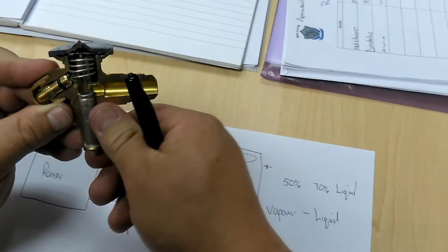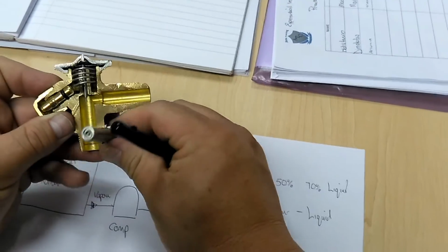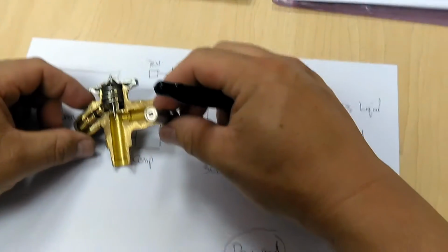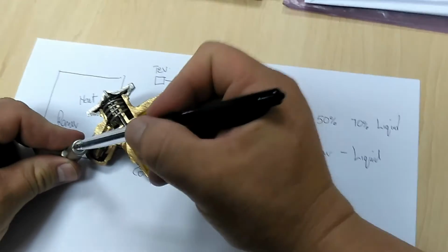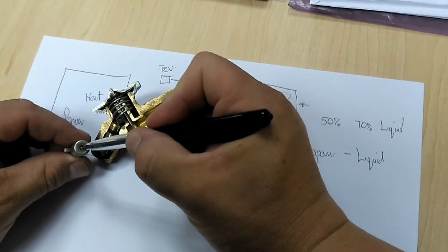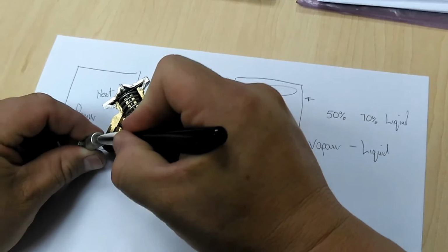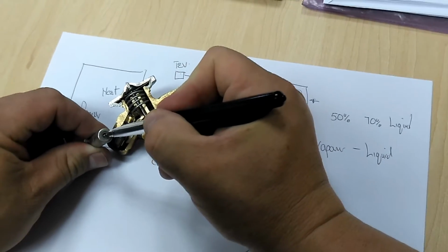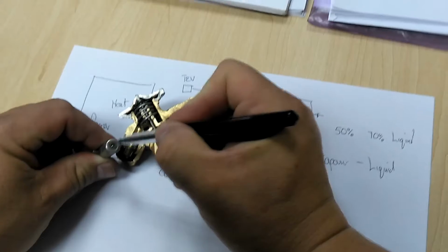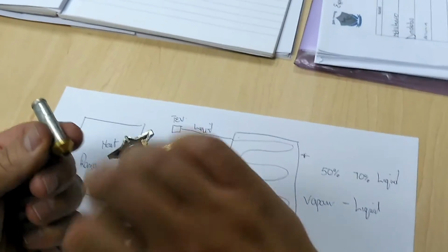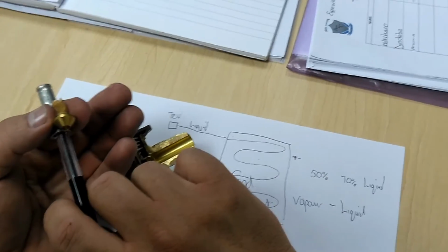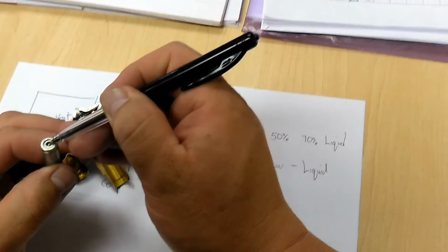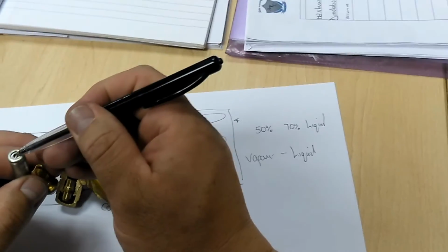So to understand this clearly, we're going to remove this part over there. As you can see, our function over here, we have the needle itself, and we have the pin. By pushing the pin in over here, as you can see, it moves, all right? By moving this pin, we can let the refrigerant liquid pass through this part over here. By passing through into the orifice, it expands from a liquid state to a vapor state.